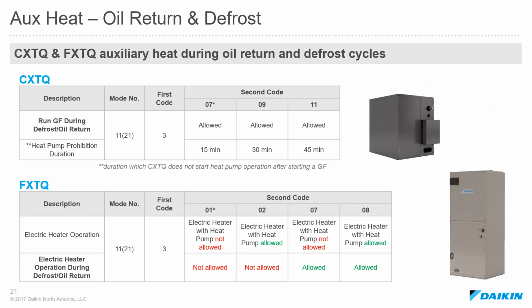So one great benefit of having this auxiliary heat source too is we can run it during some of the special operation modes like oil return and defrost, and that's available on both the A coil, the CXTQ, and the multi-position air handling unit, the FXTQ. So these are the field settings associated with that. Essentially, you can set how long the gas furnace, once it comes on to help out during oil return and defrost, is going to run: either 15 minutes, 30 minutes, or 45 minutes before it shuts off. And then on the FXTQ, these are the two settings associated with running it in that special operation mode, but you can have it provided or used as a supplemental source in heating, or not used and only used in defrost and oil return.